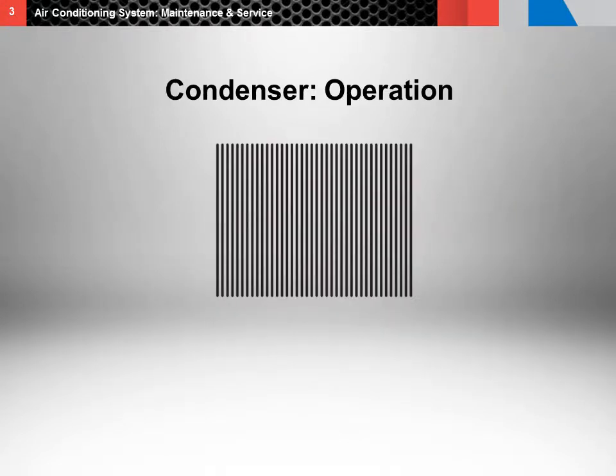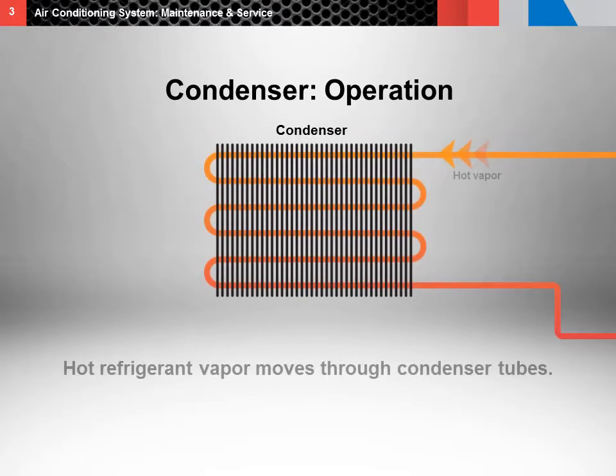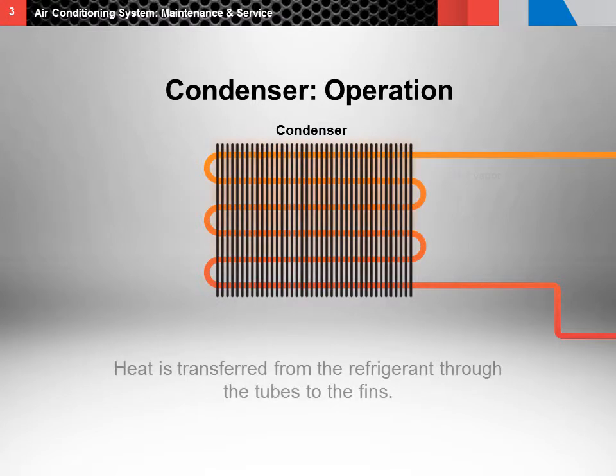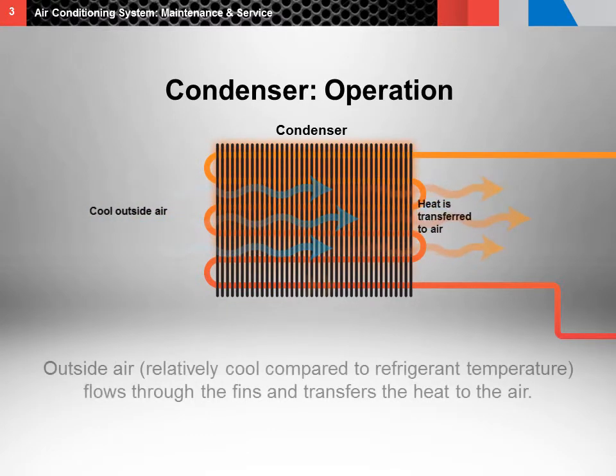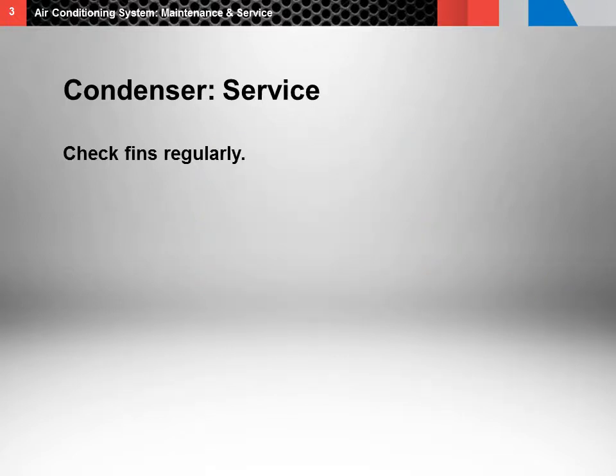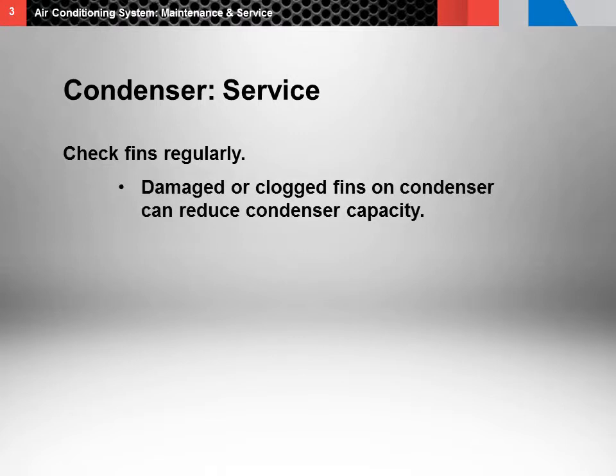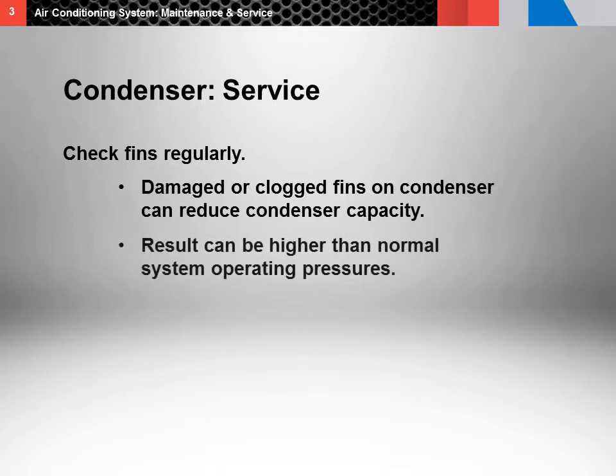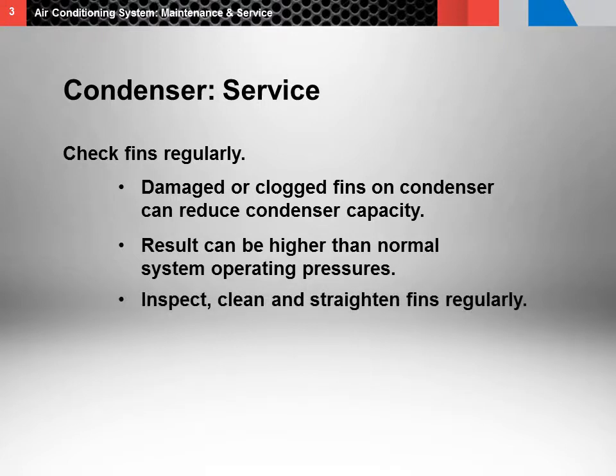The next component to look at is the condenser. The condenser is like a radiator for refrigerant. The hot refrigerant vapor travels through the condenser tubes and heat is transferred from the refrigerant to the fins. Then, as the cool outside air flows past the fins, heat is transferred to the air. The vapor is cooled and condensed and turns into liquid. Damaged or clogged fins on the condenser can reduce condenser capacity, resulting in higher than normal system operating pressures. So it's important to inspect, clean and straighten the condenser fins on a regular basis.